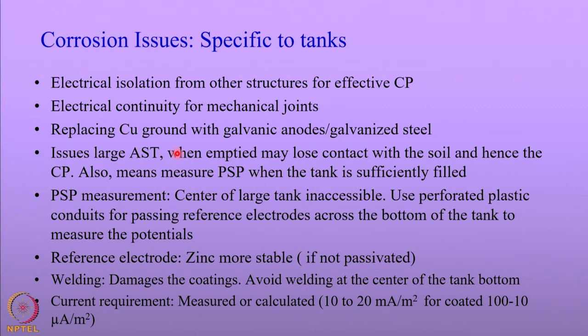Storage tanks are earthed using copper, but whenever you go for cathodic protection systems, these are replaced with galvanic anodes or galvanic steels. There are especially issues associated with above ground storage tanks because when you empty the tank, the contact between the soil and the tank bottom becomes loosened, making it hard to measure the tank-to-soil potentials. So tank-to-soil potentials are generally measured only when the tank is completely filled up.